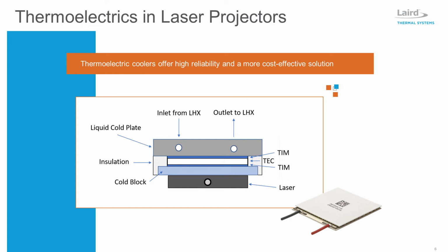In this laser projector, a thermoelectric cooler is mounted between a cold plate and a cold block. Placed around the perimeter of the thermoelectric cooler is an insulation gasket. While the cold block is attached to the laser in the projector, the hot side of the thermoelectric cooler is attached to a cold plate that circulates coolant back to a liquid heat exchanger.